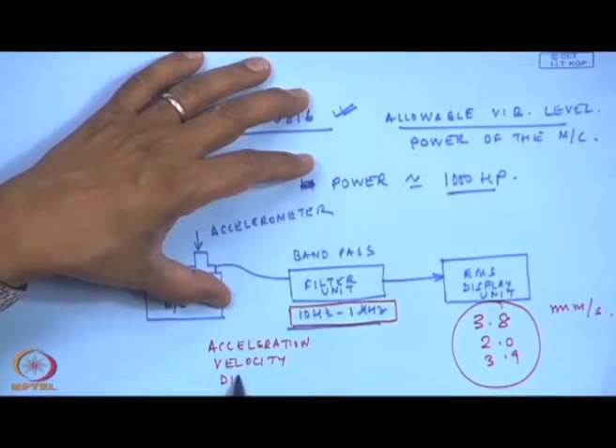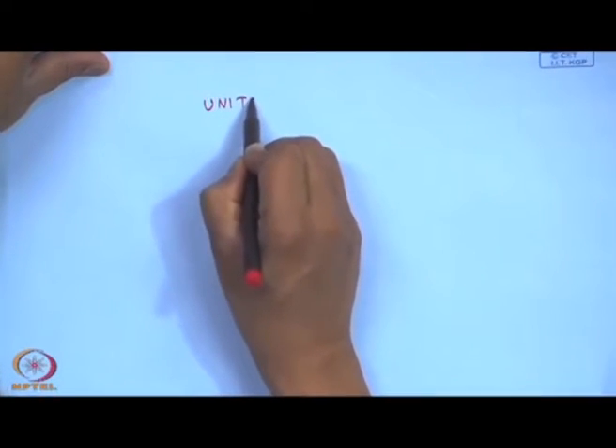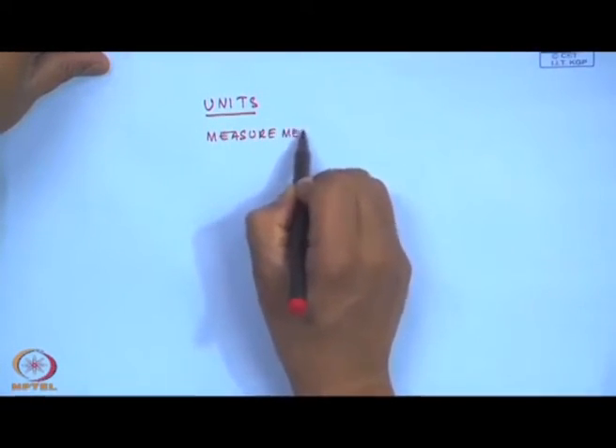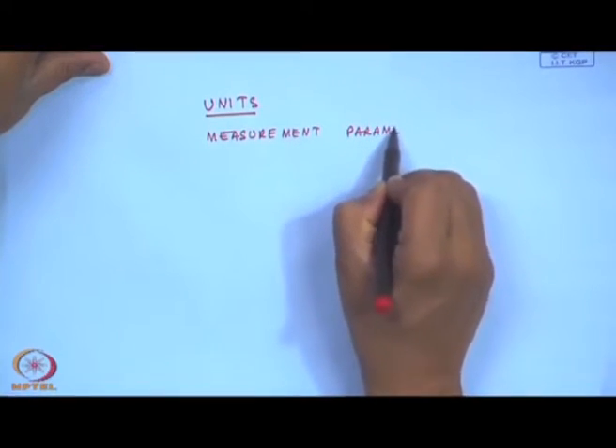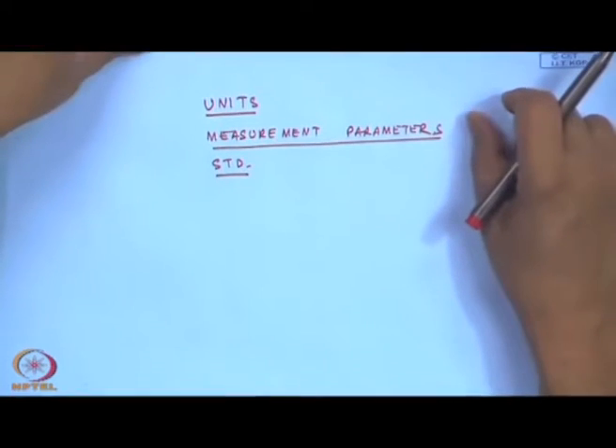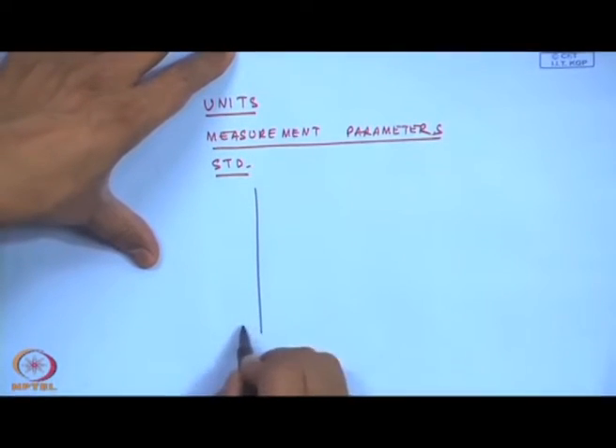For example, once you are doing trending — because with a simple electronic integrator I can move from acceleration and get the velocity or displacement values — one has to be careful about the units and the measurement parameters. If somebody is strictly following the standard, these errors will not creep in, and one has to be careful because in such measurements, as I just showed you for the case of the motor-gearbox system...